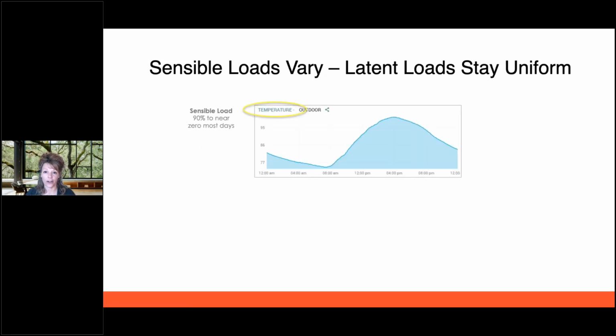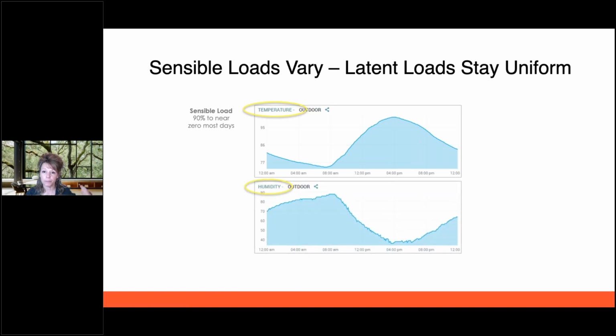So sensible loads vary throughout the day. If you look at this chart here, at 8 a.m. in the morning, we're at about 74 degrees. We go to 4 o'clock in the afternoon and we are at around 93 degrees. So the sensible loads will vary drastically throughout the day. Now, if you see here on these charts with the outdoor humidity, as I said, when the temperature is lower, the humidity is higher. When the temperature is higher, the humidity is lower. But in reality, the latent loads are exactly the same. We have a 71-degree dew point, whether it's 8 o'clock in the morning or 4 o'clock in the afternoon. We have the same amount of moisture in the air.